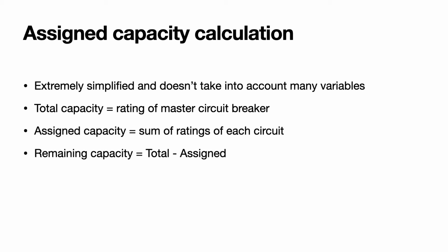I said this is extremely simplified because you're obviously not going to have every single last device in your house turned on at the same time. So you're unlikely to reach a situation where the total capacity is being consumed in the house. If you look into what electricians do, they calculate what's called a load calculation, which is a better estimate of what the maximum load will be in a particular house. When they consider adding a new device like a charging station to a house, they'll redo the load calculation, and that will determine whether the capacity of the service panel is exceeded. But this assigned capacity calculation is meant to be a starting point for understanding how that works.